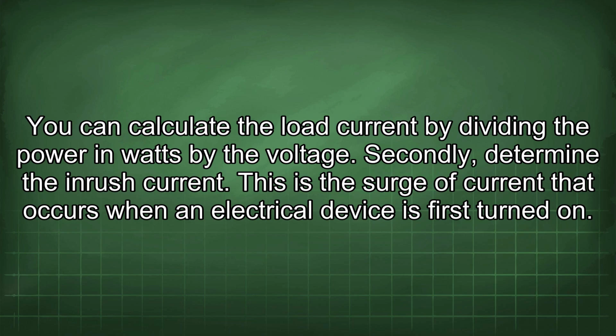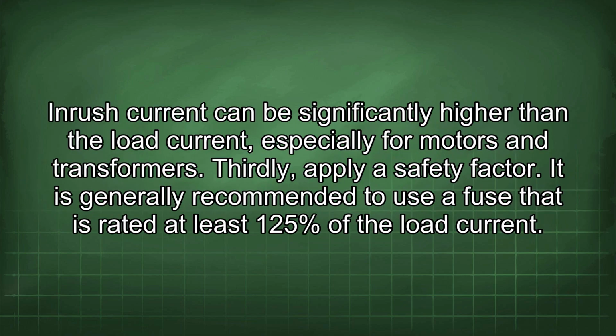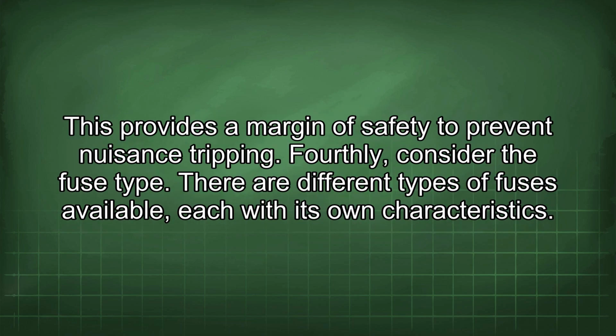Secondly, determine the inrush current. This is the surge of current that occurs when an electrical device is first turned on. Inrush current can be significantly higher than the load current, especially for motors and transformers. Thirdly, apply a safety factor. It is generally recommended to use a fuse that is rated at least 125% of the load current. This provides a margin of safety to prevent nuisance tripping.